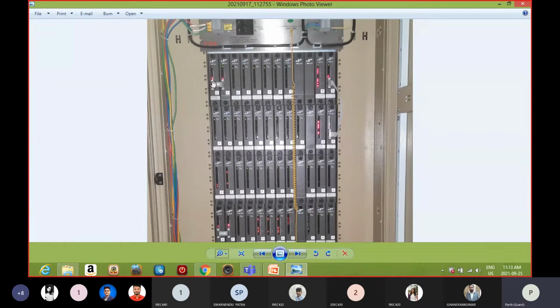So here you can see in this controller, how many IO cards? 1, 2, 3, 4, 5, 6 - this is a pair. 7, 8, 9, 10, 11, 12, 13, 14, 15, 16, 17, 18, 19, 20, 30, 31, 32, 33, 34, 35. So we have 35 IO cards in one controller, and in each IO card we have 16 channels. Channel means the pin we use. So 35 into 16, so I can handle 560 IOs through one controller.